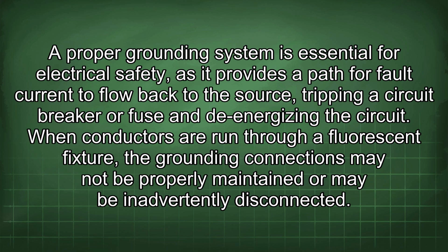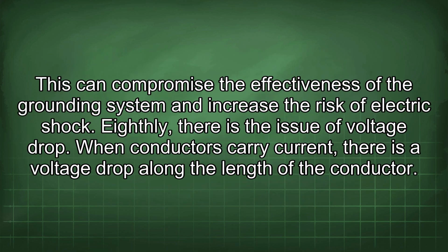When conductors are run through a fluorescent fixture, the grounding connections may not be properly maintained or may be inadvertently disconnected. This can compromise the effectiveness of the grounding system and increase the risk of electric shock.